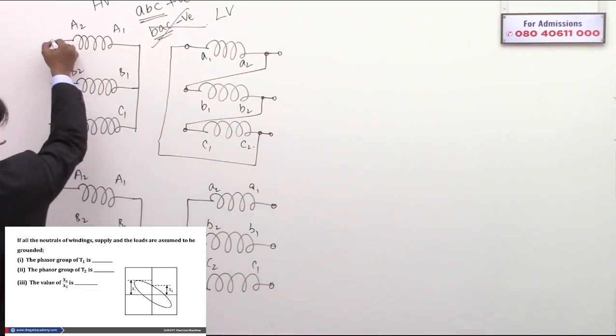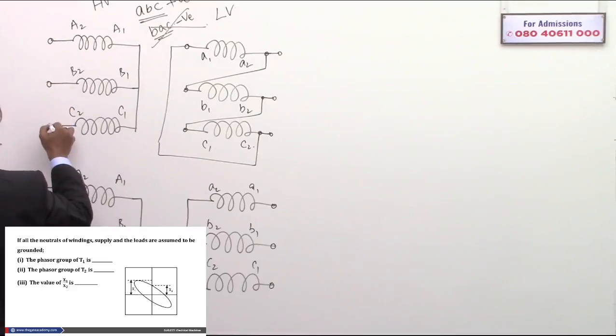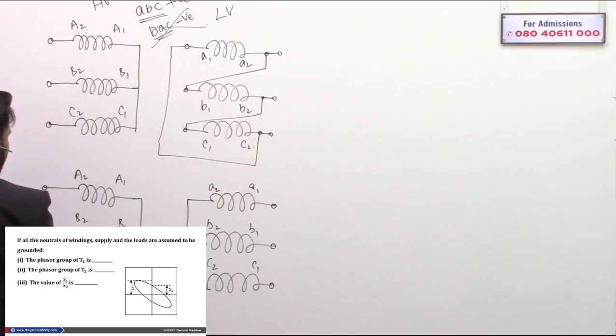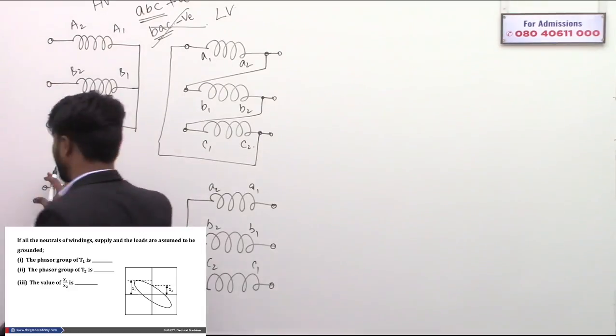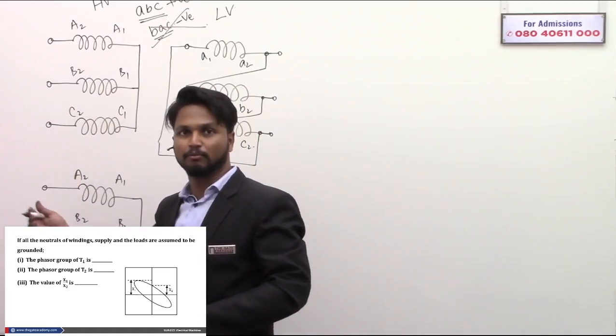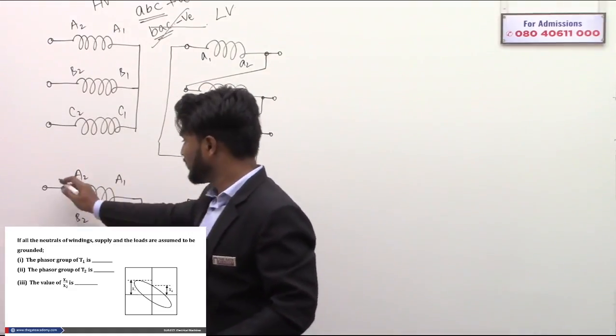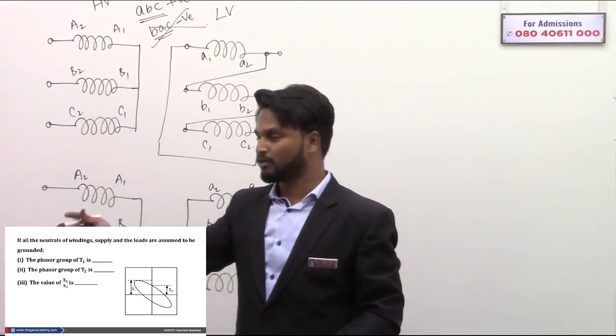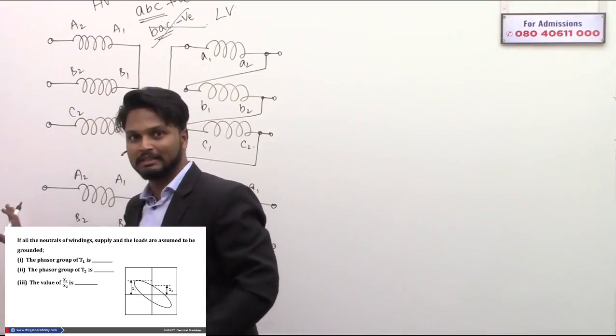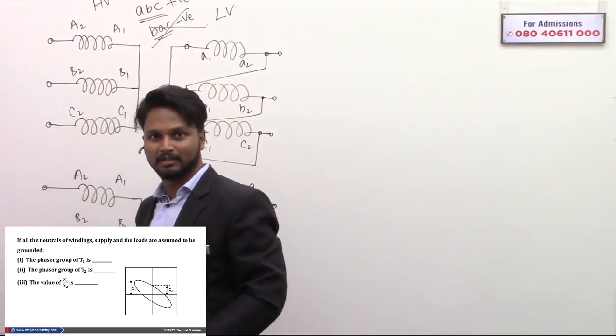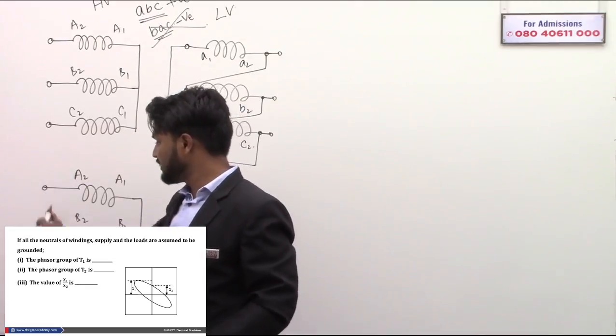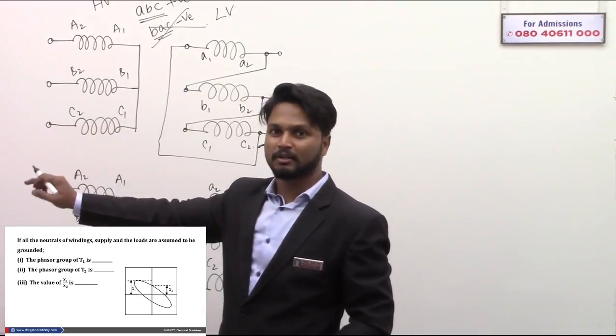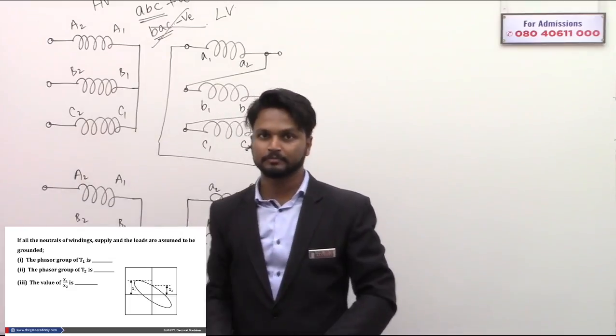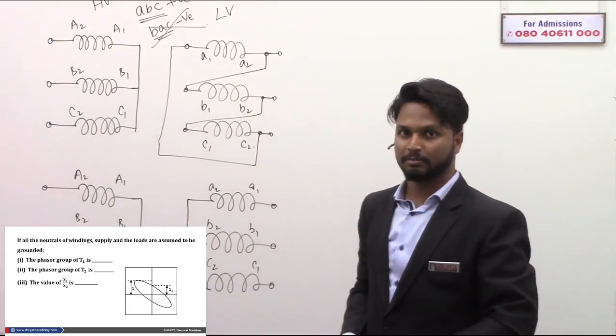The bubbled terminals mean these terminals are given supply, or from these terminals we take the line voltages. So bubbled terminals will give you line voltages, or you give supply to these windings from the bubbled terminals. These indicate the line terminals, or supply terminals.